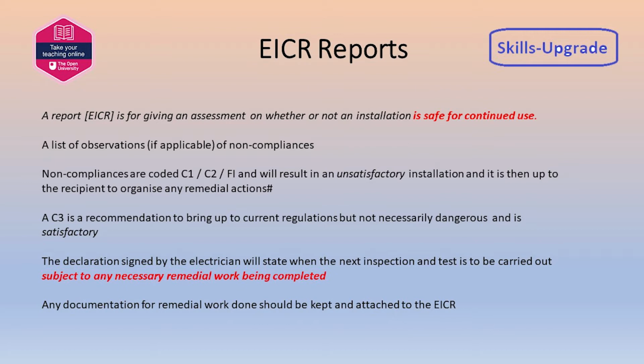Coding, which we will come on to shortly, consists of two unacceptable outcomes, C1 and C2, and FI, which is further investigation required. The report, as shown in Appendix 6, states that if C1 and C2 have been identified, the installation is unsatisfactory.